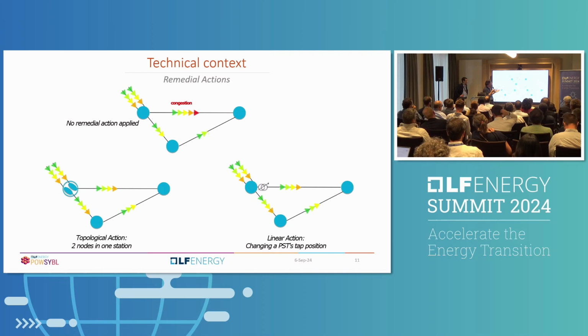If you have some way to decouple the different bus bars, then you can have one line connected to the next line on the output, and here the same, one line connected to only one line. So now if each arrow is 100 megawatts, for instance, here you had 800 megawatts coming in and 800 coming out, but with 500 at the top and 300 at the bottom. Here you have, once again, 800 in, 800 out, but you have decoupled the two bus bars, and so you have 400 megawatts on the top line and 400 megawatts on the bottom line. So that's one way to solve congestions.